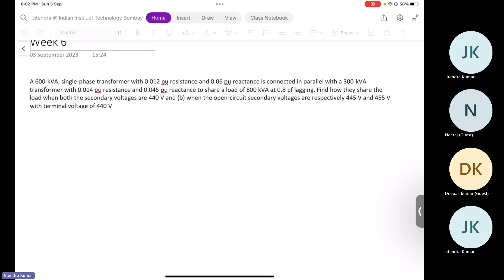have two options. One is to replace the transformer with a higher rating. That is not desirable because you will have a spare transformer. If you are replacing, you are creating a waste of a spare transformer. And in many cases, if your transformer got damaged or any problem occurred in that transformer, then one of the two transformers or one of the many transformers can supply a partial fraction of the load. So in those scenarios, it is advantageous to connect multiple transformers in parallel rather than just connecting one very large transformer to supply that load.